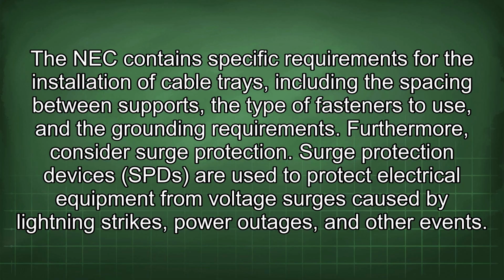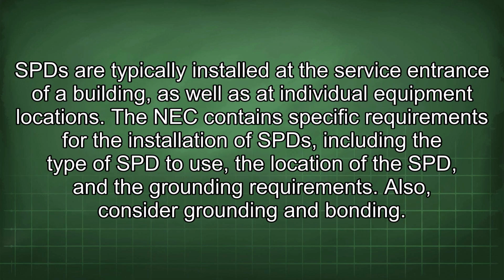Furthermore, consider surge protection. Surge protection devices (SPD) are used to protect electrical equipment from voltage surges caused by lightning strikes, power outages, and other events. SPD are typically installed at the service entrance of a building, as well as at individual equipment locations. The NEC contains specific requirements for the installation of SPD, including the type of SPD to use, the location of the SPD, and the grounding requirements.